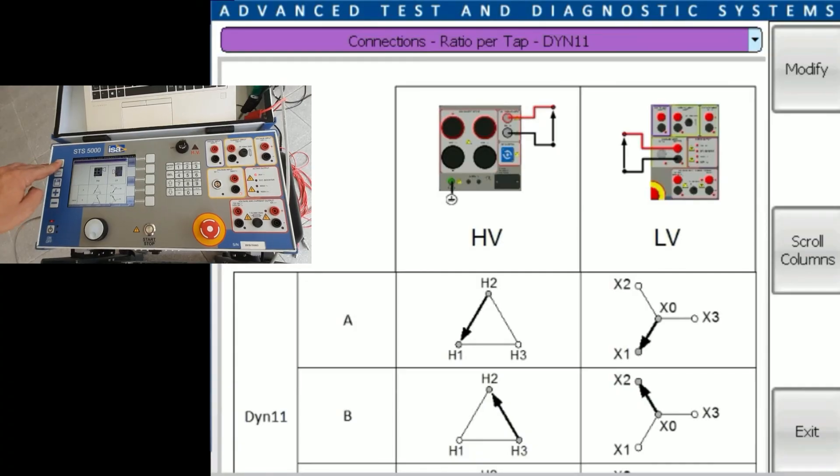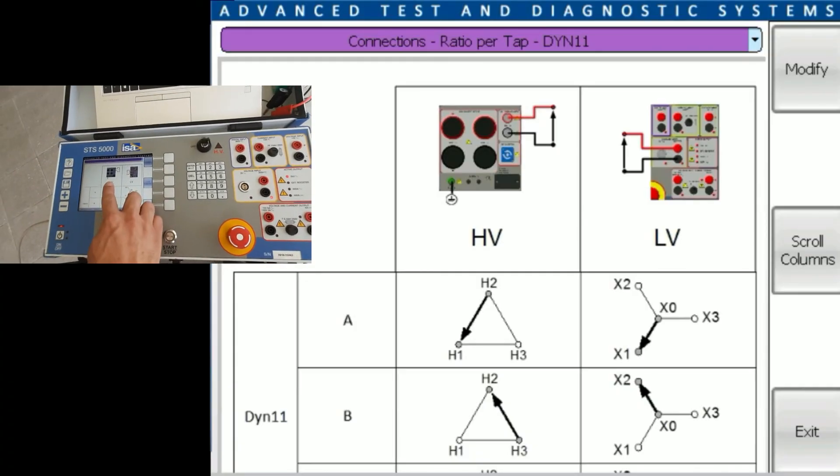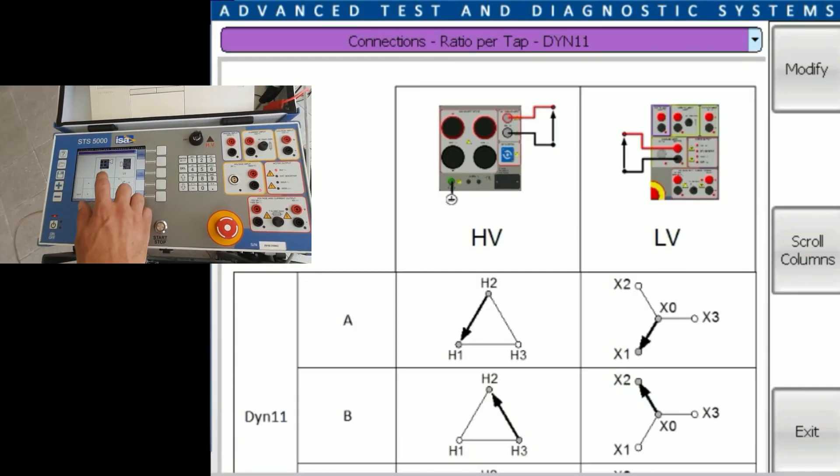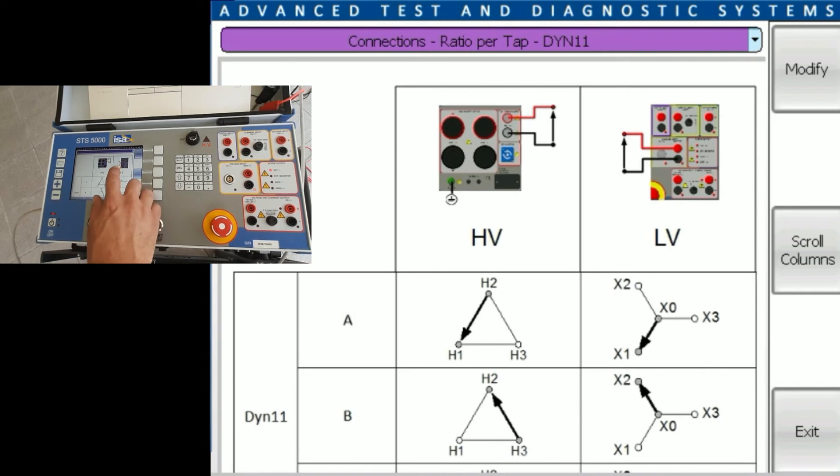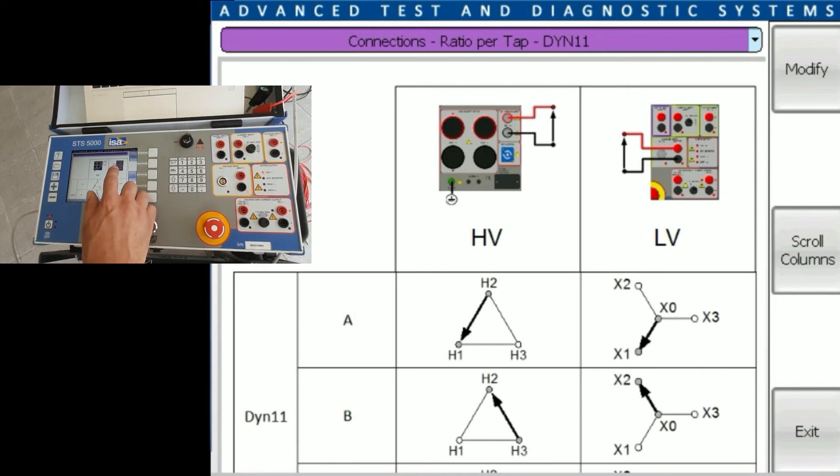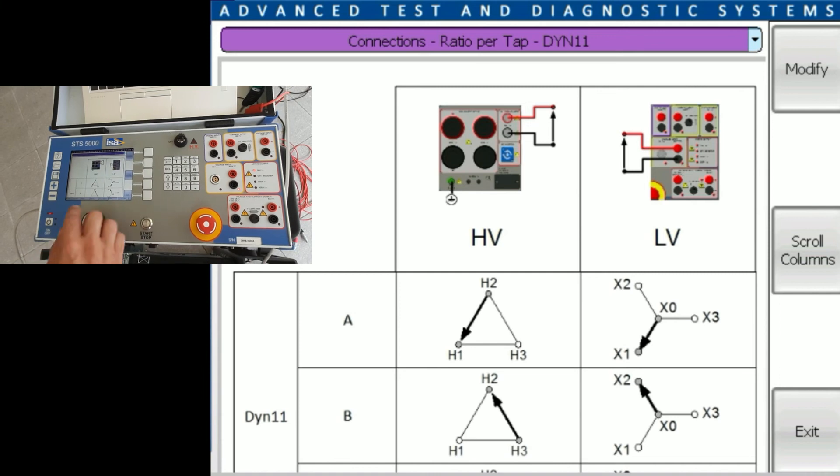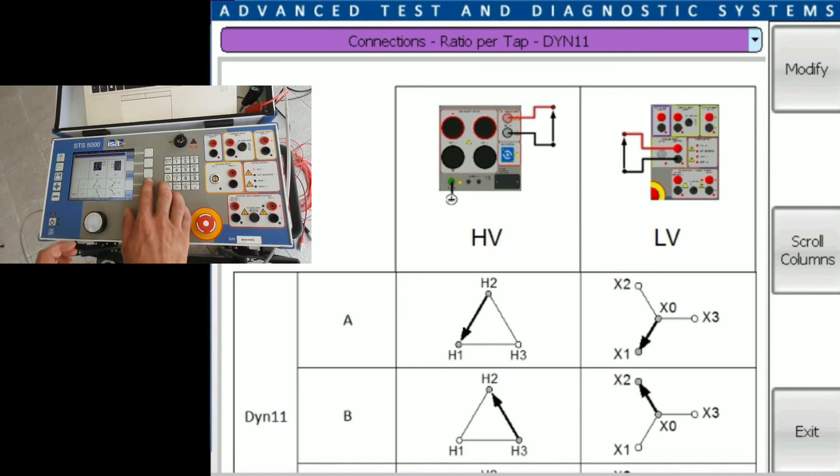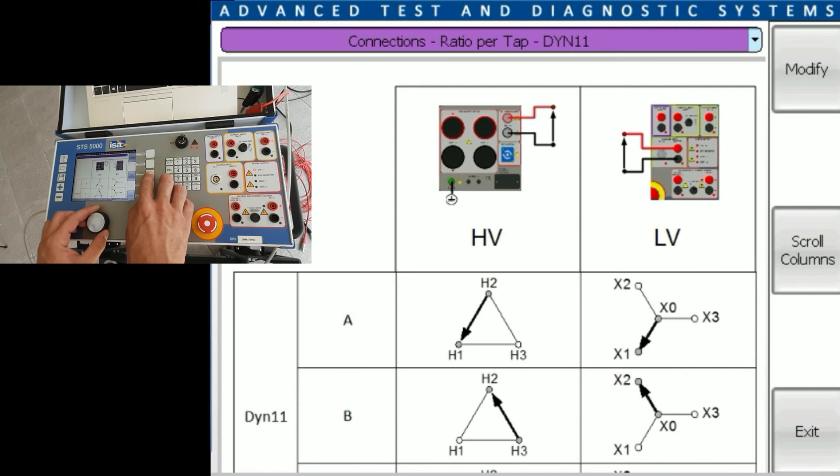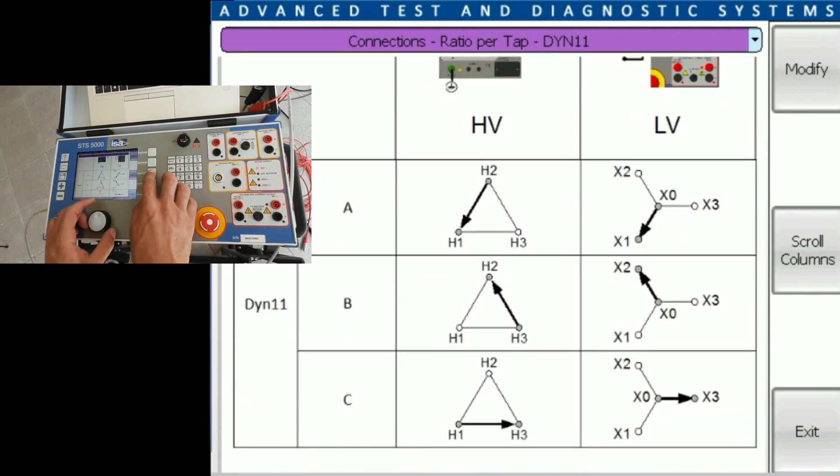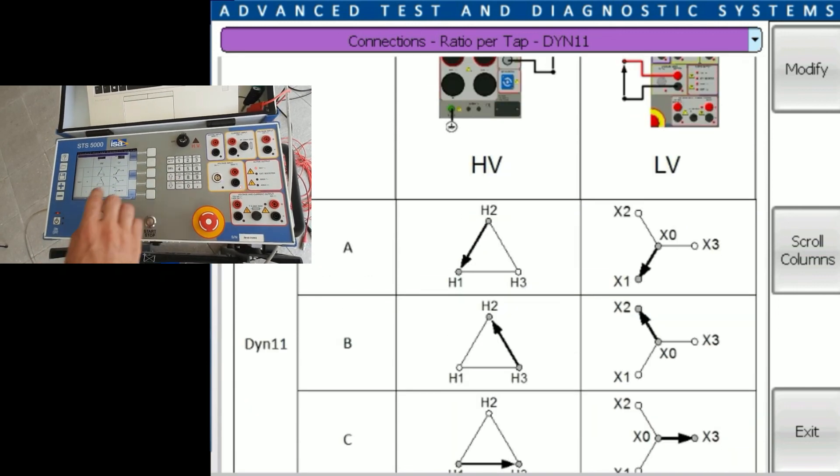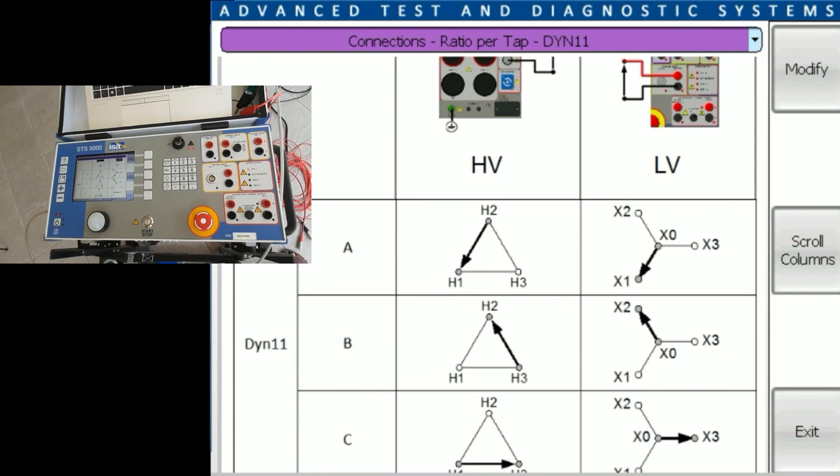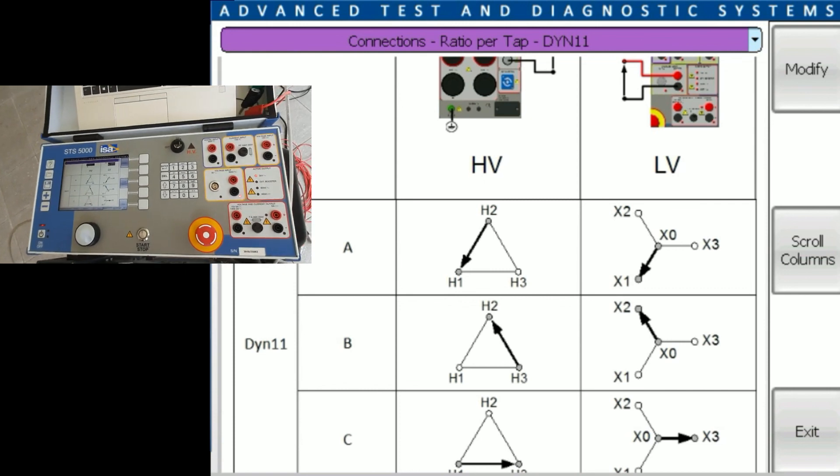And for the end, if you're not sure what to choose, just press the question mark button and you will see how you need to connect. So the 2kV output is connected on the high voltage side. The measurement from the low voltage side is connected to the 300 volt input. And here you have connections for phases A, B, and then you press scroll column, you hold it pressed and you scroll slightly below to see it for phase C. And that's what we're going to connect right now.